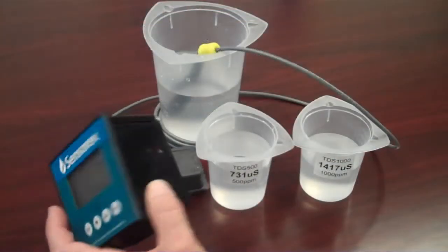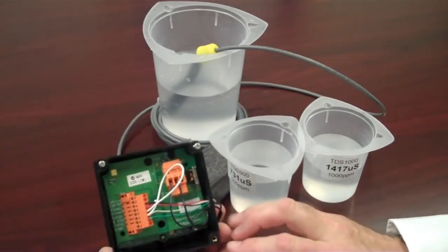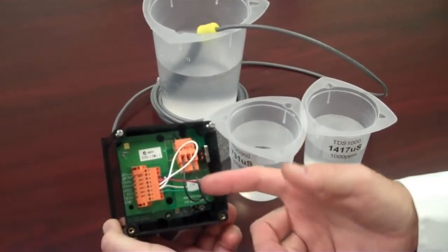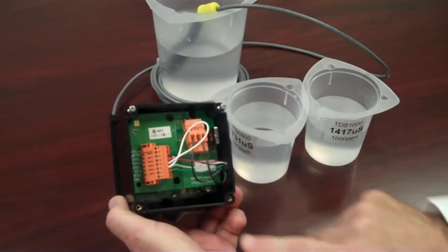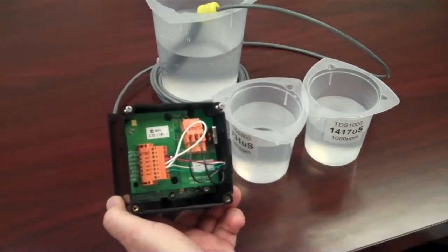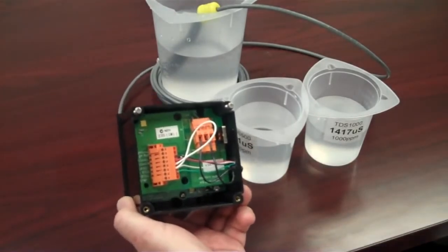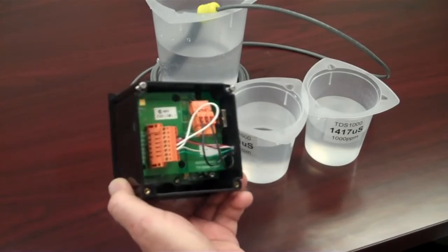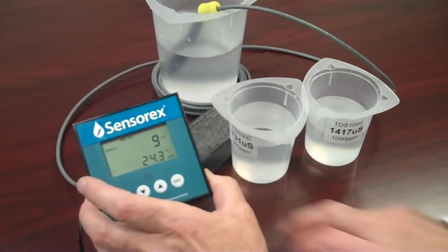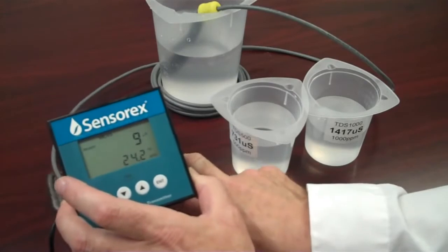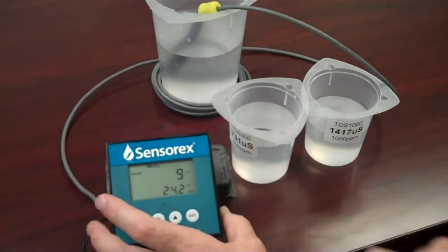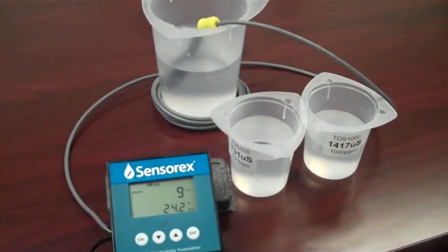To calibrate, connect your conductivity sensor to the instrument. If you have temperature sensor leads, connect these to the instrument as well. Follow the user instructions for connecting the wire leads and calibration of the sensor in the owner manual of your instrument. Most instruments will require that you select a range of measurement. Use the setup menu as shown in the user instructions.